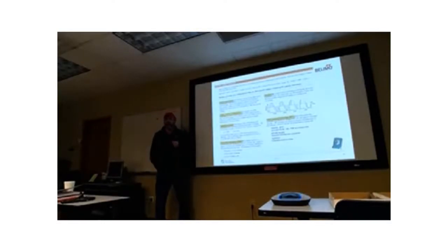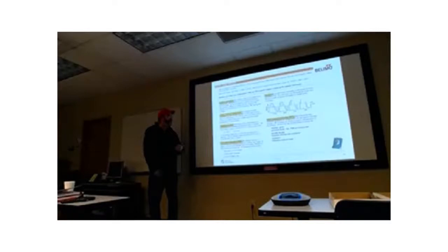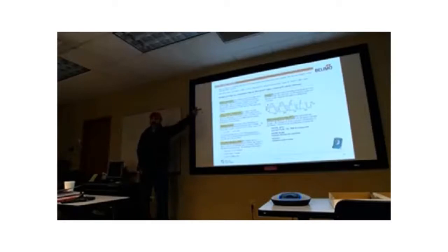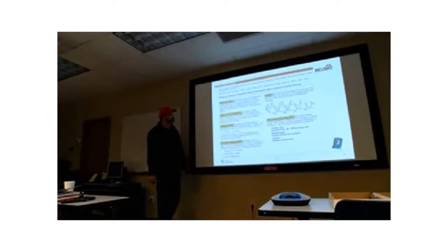The first one, I call this two position, because I think on off is probably misleading. You know what I mean by two position, right? The actuator drives to one position or goes to another position by different means. If you have a spring return actuator that's two position, how many wires do you need to operate? Two, right? All you're going to do is drive it one way, apply the voltage, and then take the voltage away, and the spring takes it back the other way. That's two wires. How about for a non-spring return? Three. Now we need three, because the motor has to drive in either direction. So this is as simple as it gets.